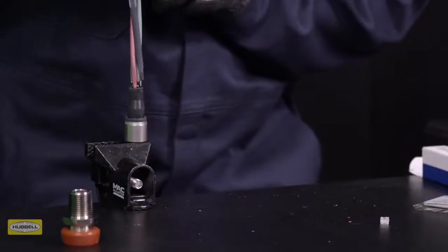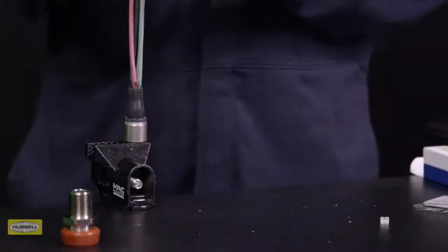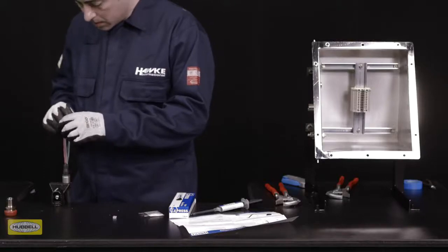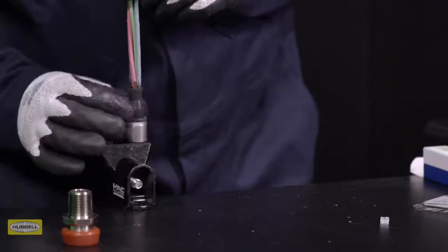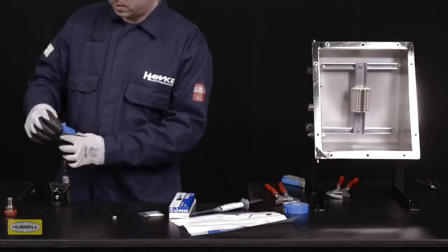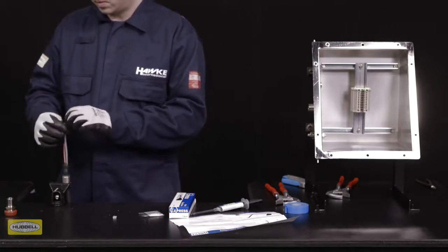Check that the resin is properly filled without any voids. Manipulate the cable cores to ensure the resin has filled any voids between them. If air pockets are present, coax them out from the resin by manipulating the silicone pot. Tape the cores so they stand centrally to the pot. If the fill level drops below the minimum level, top off the resin to the fill line.